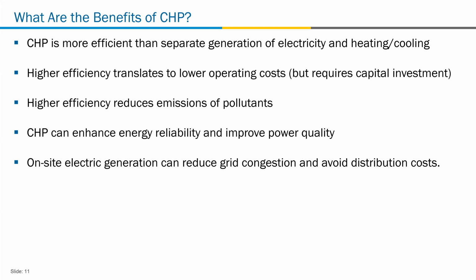So what are the benefits? We already showed you the efficiency benefits. High efficiency also generally translates into lower operating costs, but it requires a capital investment, so that's the balance we have. Higher efficiency also reduces emissions of pollutants as well as carbon emissions. CHP can enhance reliability and improve power quality, because it can be used as a vehicle where you can island when the grid goes down. When you have local generation, you improve the ability to have frequency and voltage control at your site. Also, on-site power can reduce grid congestion and avoid extra distribution costs.